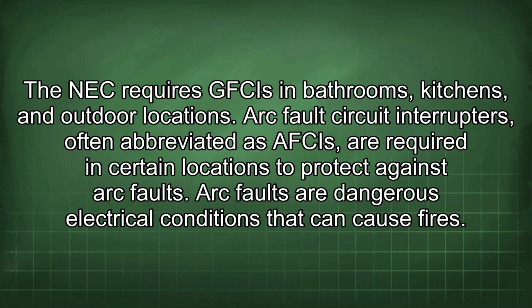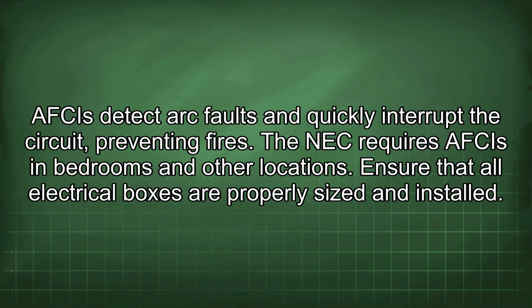Arc fault circuit interrupters, often abbreviated as AFCIs, are required in certain locations to protect against arc faults. Arc faults are dangerous electrical conditions that can cause fires. AFCIs detect arc faults and quickly interrupt the circuit, preventing fires. The NEC requires AFCIs in bedrooms and other locations.